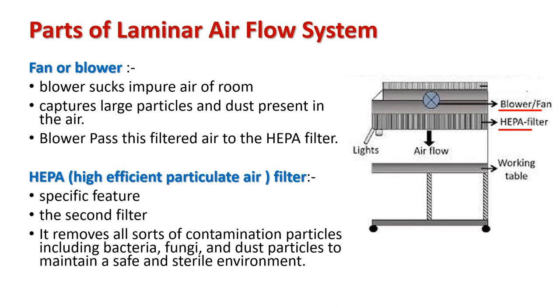The fan or blower sucks in the room air, captures large particles and dust, and passes this filtered air to the HEPA filter. The HEPA filter — High Efficiency Particulate Air filter — is the specific feature of laminar airflow and acts as a second filter. It removes all sorts of micro contaminants including bacteria, fungi, and dust particles to maintain a safe and sterile environment.